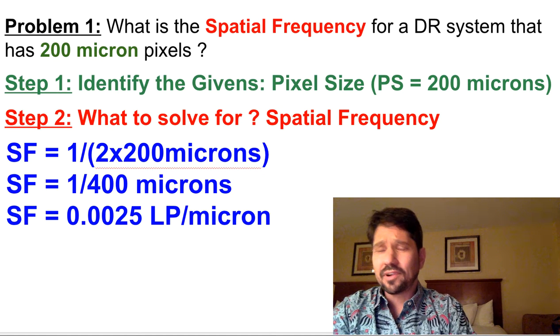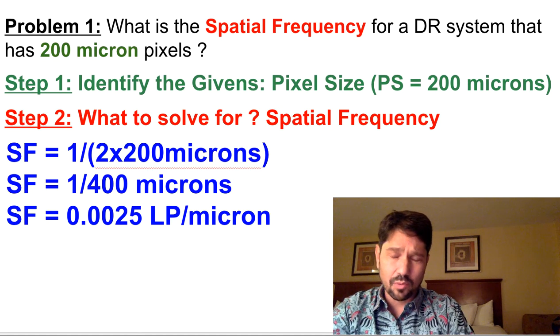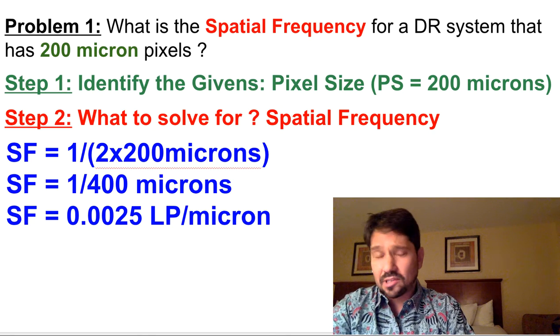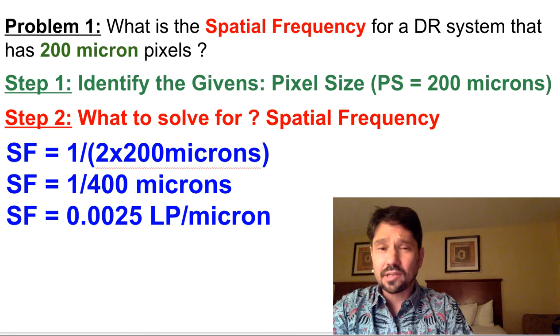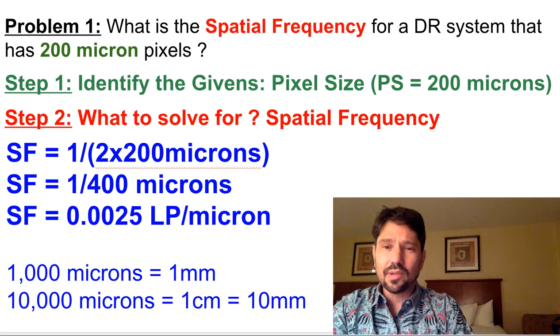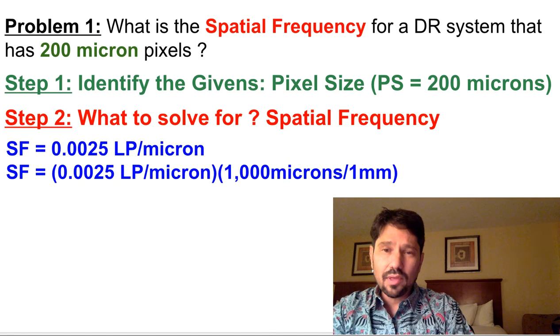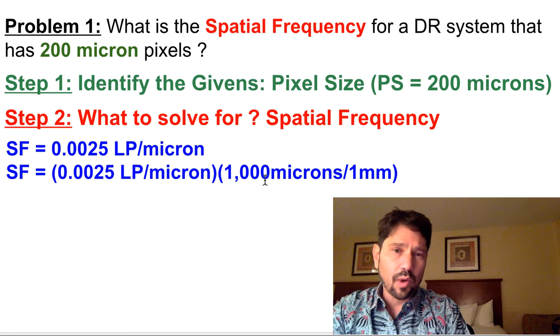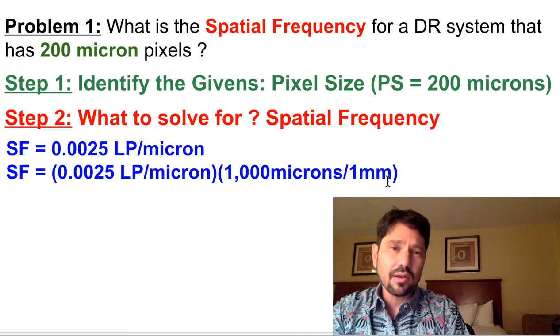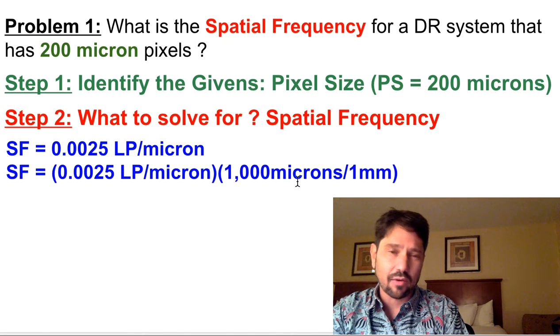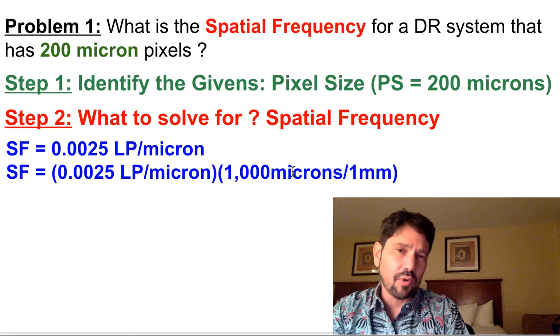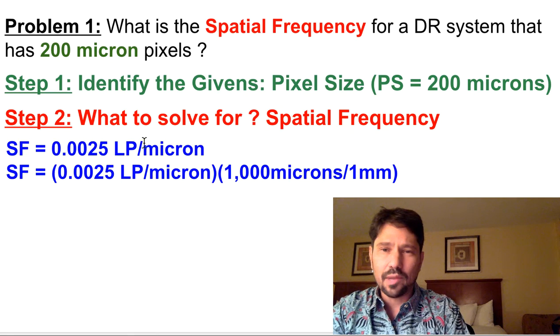But they're never going to want line pairs per micron. We're always going to want line pairs per centimeter, or perhaps line pairs per millimeter. So we'll need to convert, and we'll need to know those conversion factors. So if we've got line pairs per microns, as shown, we'll want to put microns in the numerator and 1 millimeter in the denominator, so the microns will cancel out. And this is a ratio of 1, 1,000 microns to 1 millimeter.